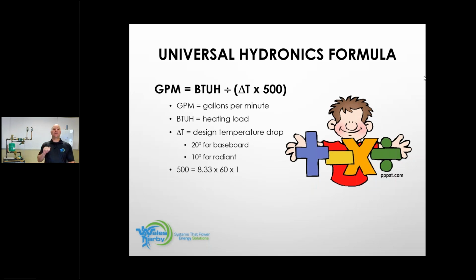And then in there we have a dividing sign, and then we have parentheses, which has our delta T symbol and 500. So the delta T symbol is what we are looking for, a temperature difference across that boiler. And I said earlier about a 20-degree delta T. So 20-degree delta T will be the most common temperature that we're going to be using in the hydronics world.